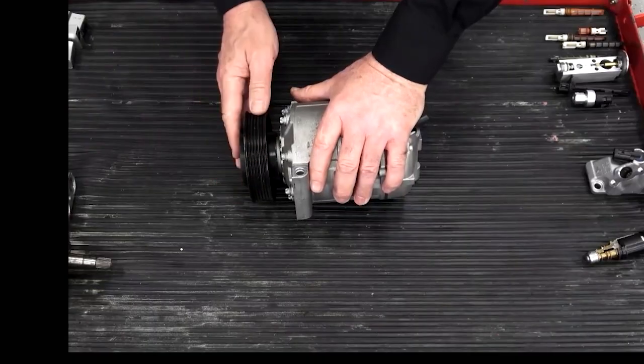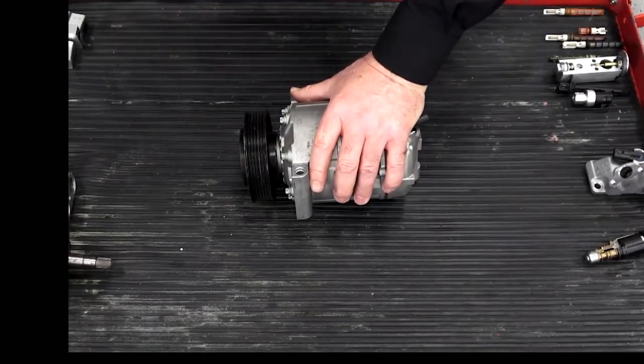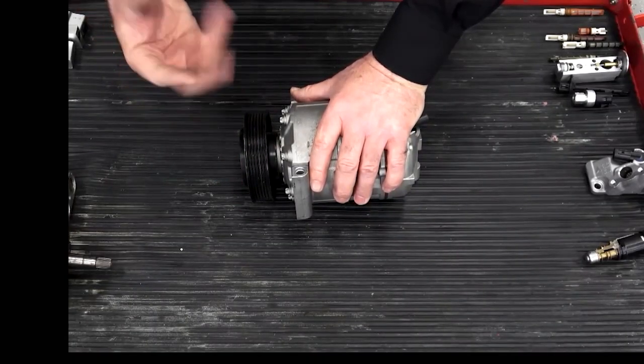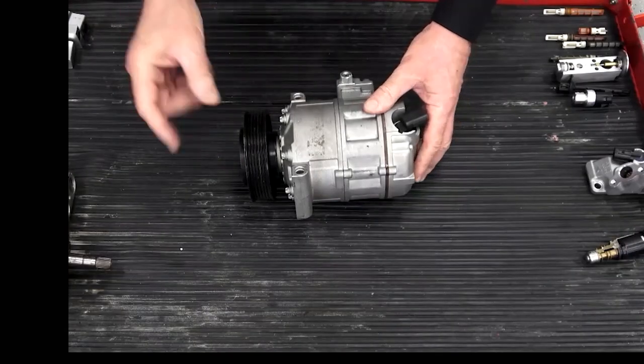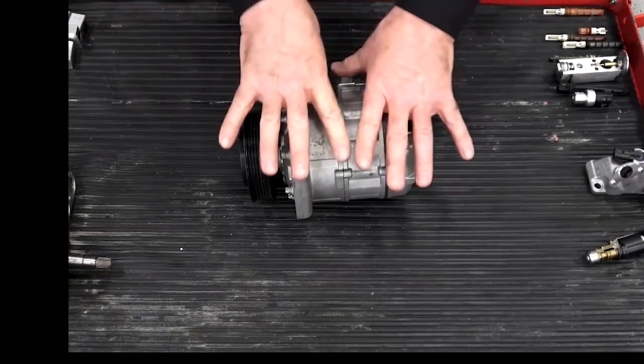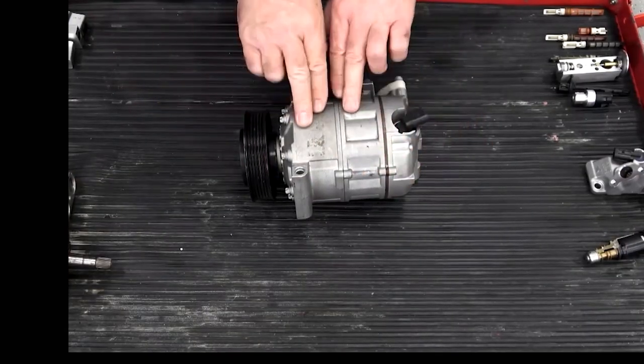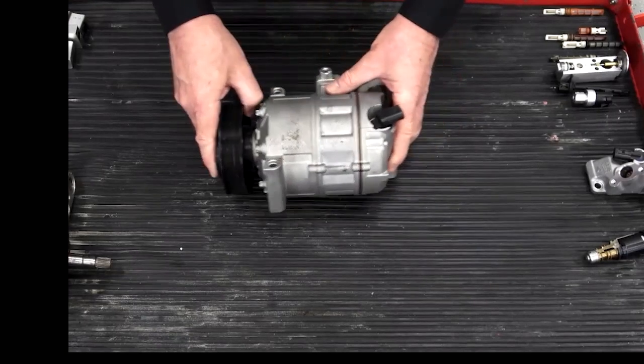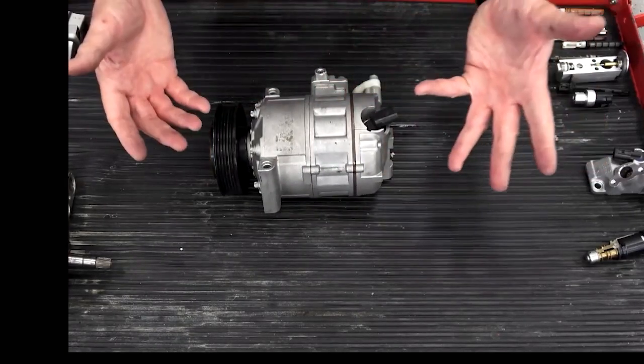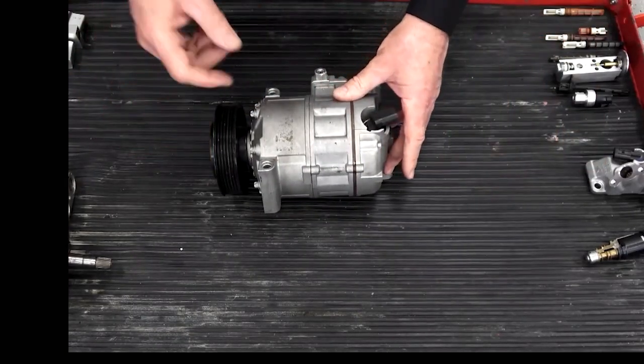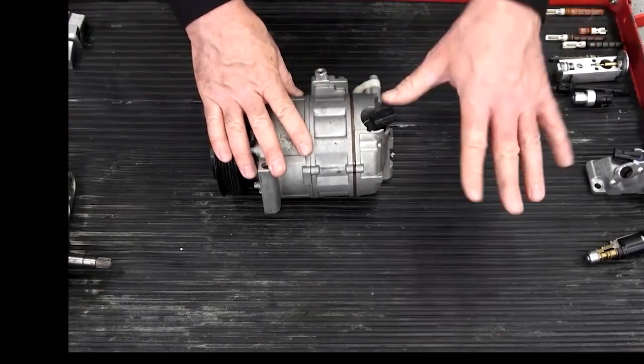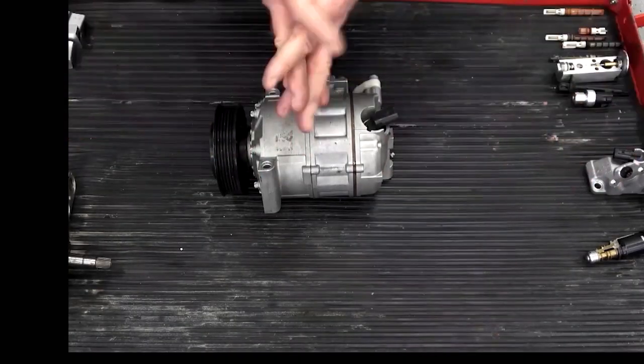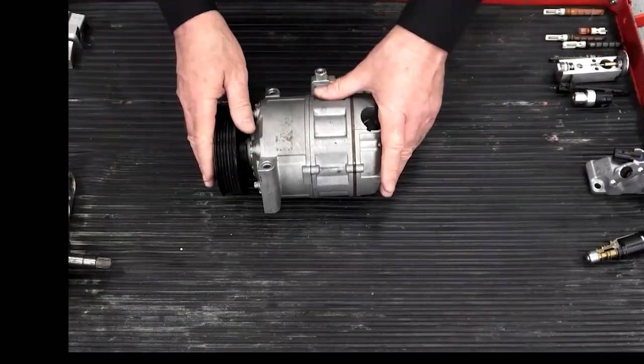Now, I want to caution you here, a couple of things. Number one, we have a tech line here at our training center. We get a lot of calls about these types of compressors where the shop has replaced the compressor several times, but it doesn't appear to be working. In other words, the high side pressure is way low and the low side pressure is way high. In fact, most often the two pressures are almost equal, right?